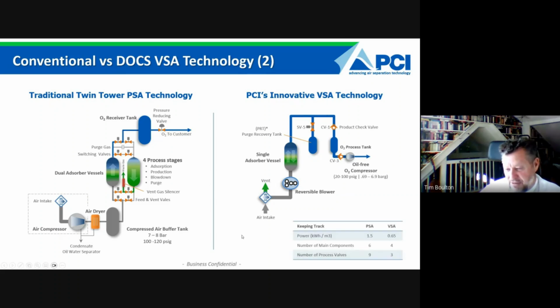What you can see here, I think that'll come up here, is if you look at the power requirements, we'll get back to that in a minute, but the number of main components in the VSA is less, as you can see here, and the number of process valves is also significantly less. What this means for you, in effect, is that the VSA systems are more robust, and they require a lot less service and maintenance.